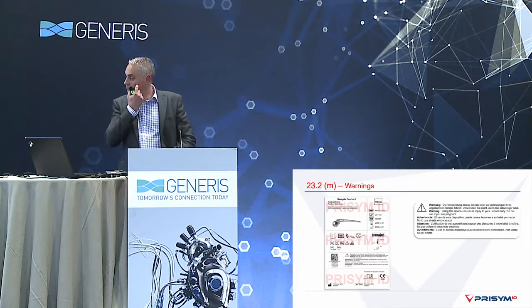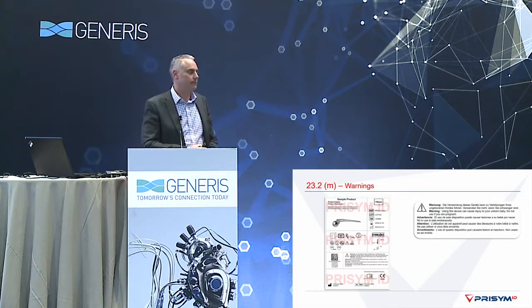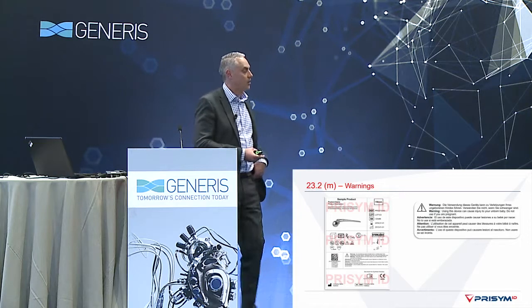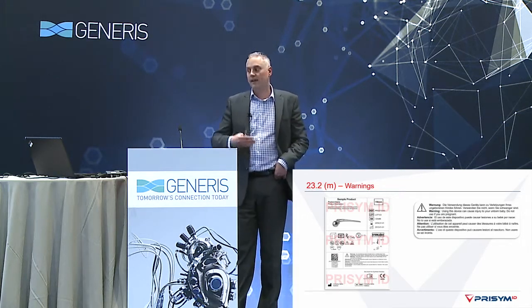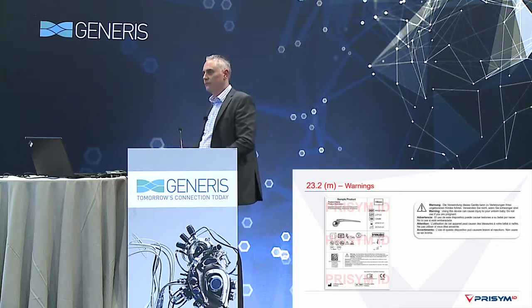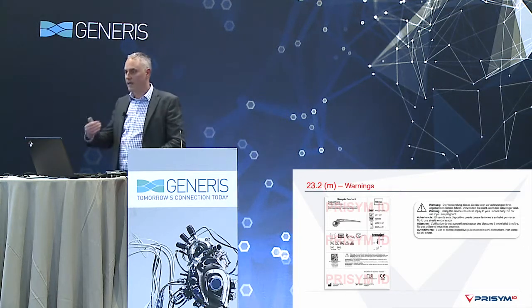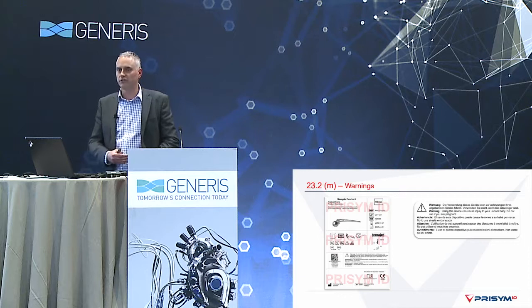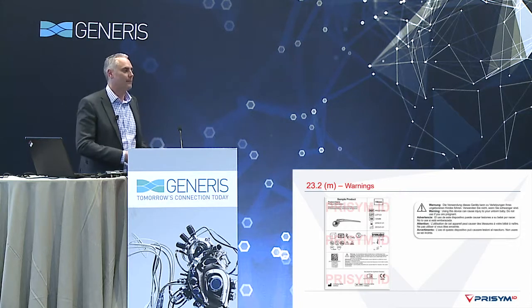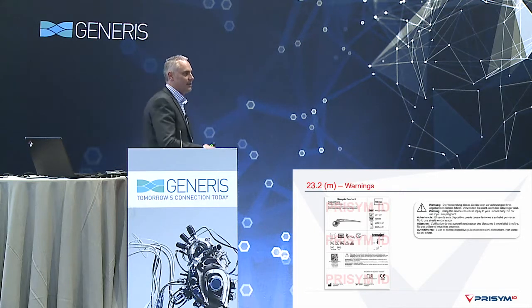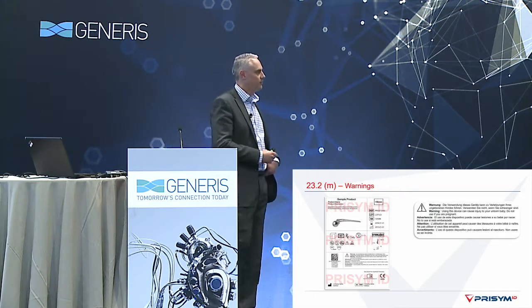Warnings. It's down to medical device manufacturers which information you see is critical, but EU MDR says important information that your customers or your users must be aware of to use a device should be on the label. Now, it is down to you to interpret what that means and what is critical information that's needed for the use of your medical device.